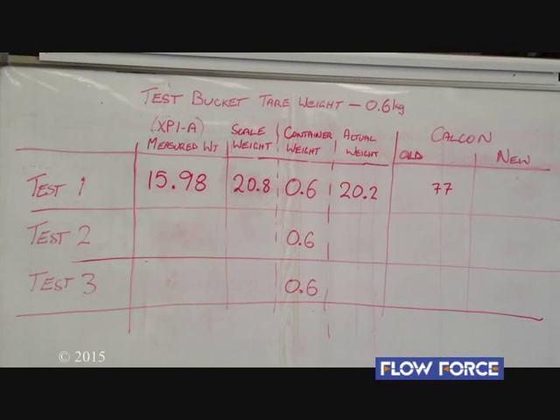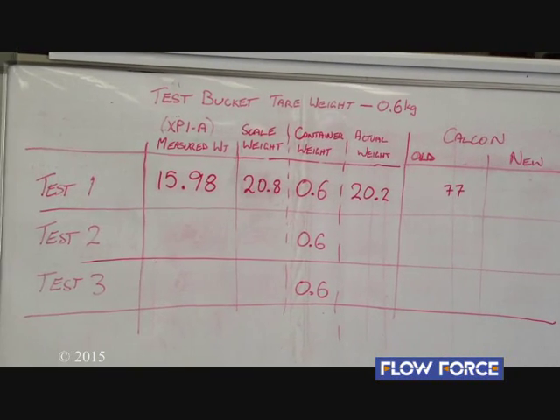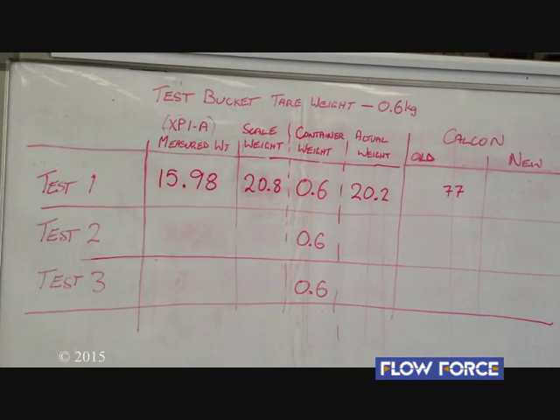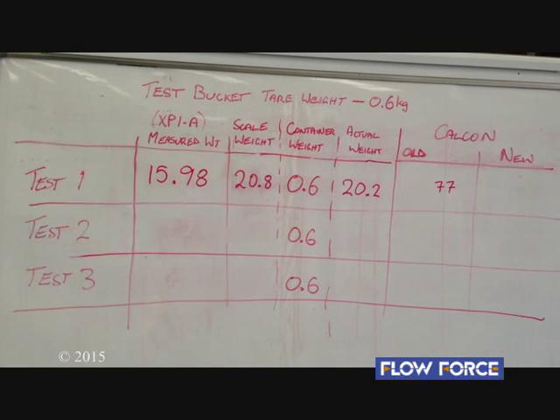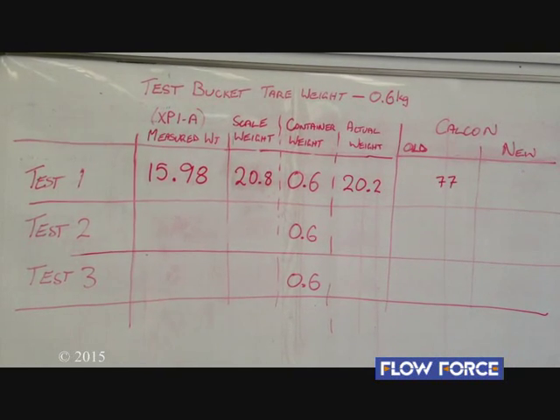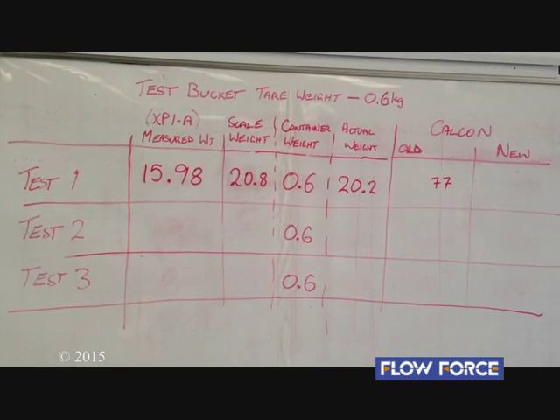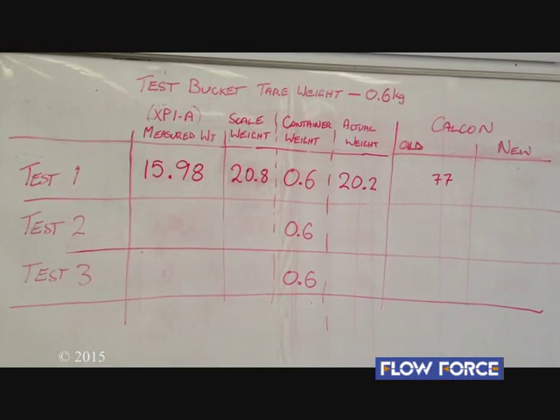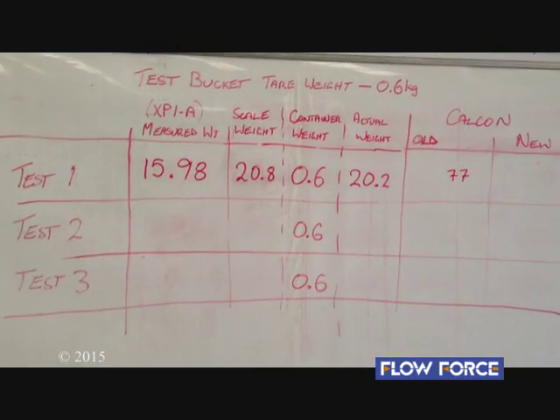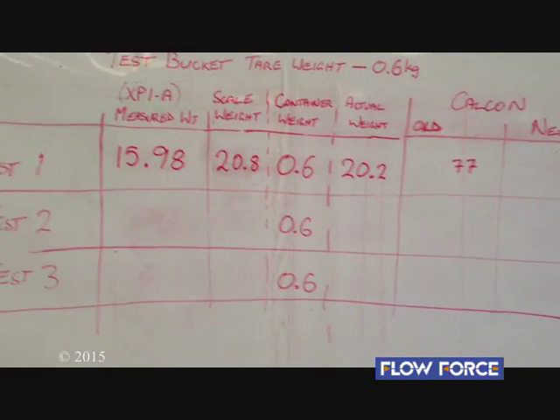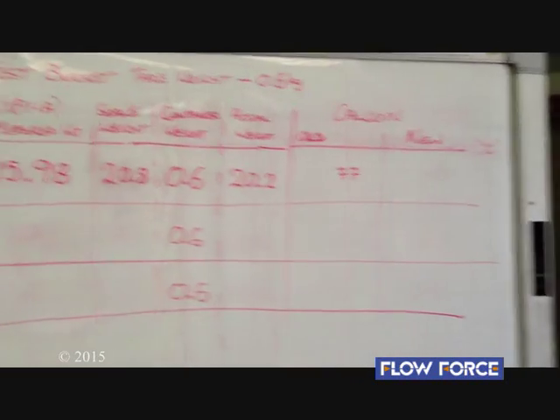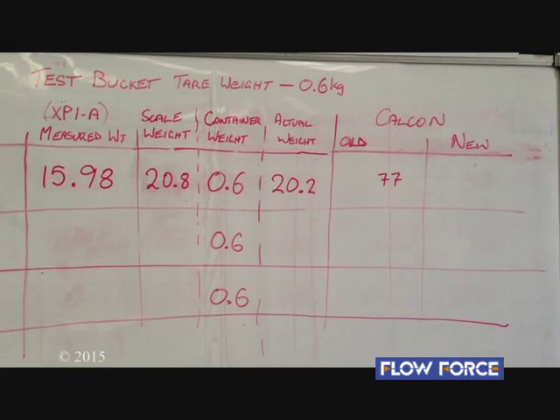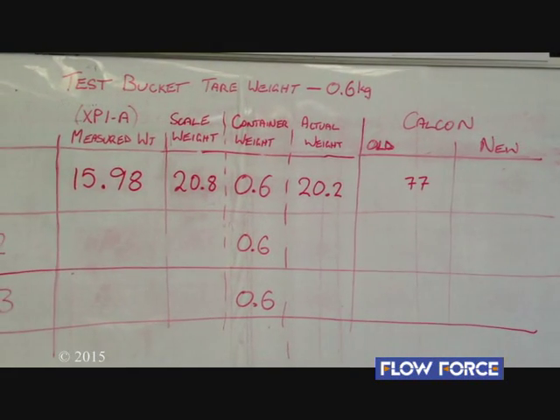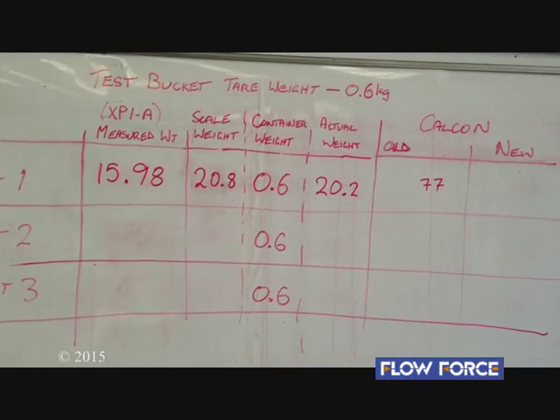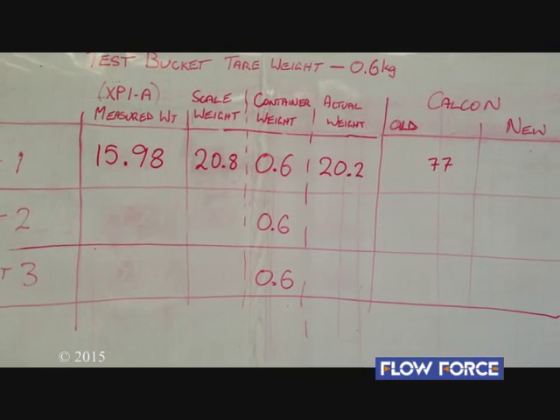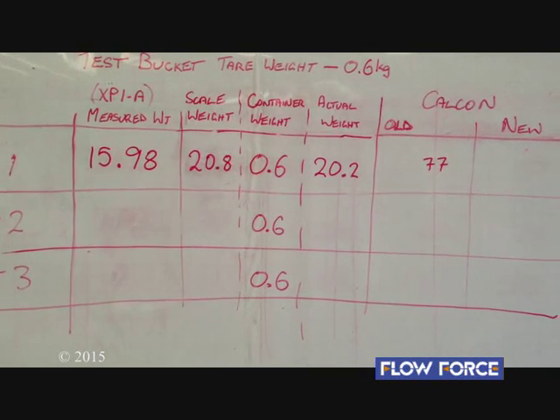So you'll see we've marked up our test sheet. The XP1 controller said it had 15.98 kilograms through. Our scales weigh 20.8 minus the 0.6 of a kilogram for the bucket, leaves us with an actual mass of product of 20.2 kilos. You'll note that we'd actually checked what the calcon was previously, and it was 77. We'll now place these figures into the XP1 controller and show you how to do the calibration.